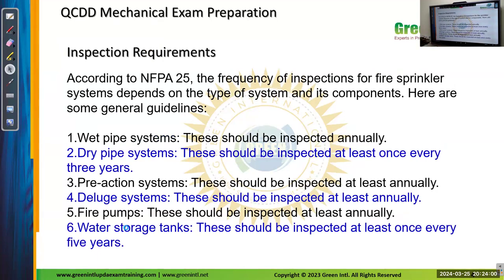So, inspection requirements. As per NFPA 25, the frequency of inspection of sprinkler systems depends on the following types. Wet pipe systems should be inspected annually. Dry pipe systems should be inspected at least once in every 3 years. A pre-action system should be inspected at least annually. Deluge system should be inspected at least annually. And fire pumps should be inspected annually. In that table, you will get all these details. But you must be very aware of whether they are asking for inspection or testing, because while reading the questions you tend to confuse inspection with testing.